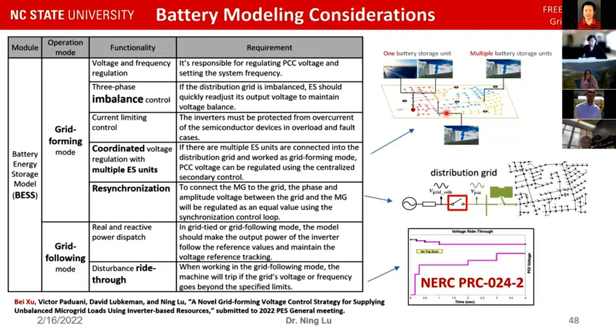That's actually a lesson learned. We found that when we designed this energy management algorithm and ran it on OpenDSS, everything was so perfect. But once we connected to the HIL team, it started to break things down - it either ran the storage at 120% of its capacity, or broke the system down without enough ramping, or the whole thing just fell apart. That's why we try to connect the two kinds of simulation together, to see this without a field test. If we don't have such a high quality digital twin of the system, we would have to rely on laboratory tests or field tests to reveal these problems. But right now, through the modeling, we can do that.